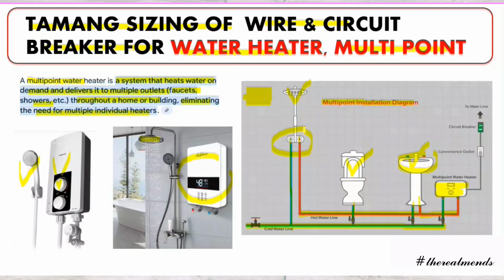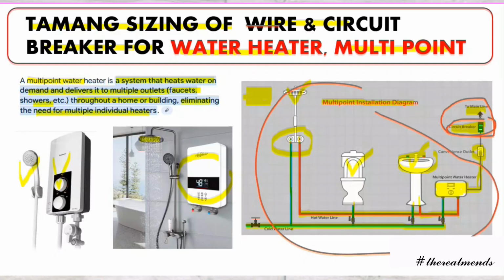And then, for the water heater to work, we need electrical power. You see, this is the outlet, where we tap. It has a cord. For this outlet, you can use a GFCI, ground fault circuit interrupter, for wet areas. And then from a circuit breaker, going to the main line. So the purpose of our discussion is from here. We will focus only here. We need to determine the main line, the wire and the circuit breaker, in order to supply the water heater. The other portion is plumbing works. But we need to focus on this side, the main electrical side.